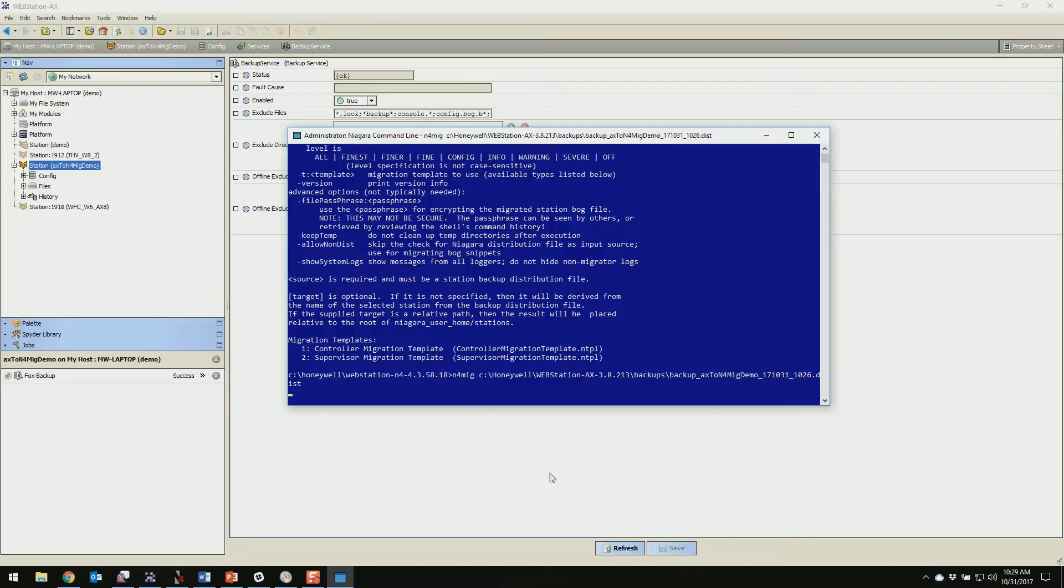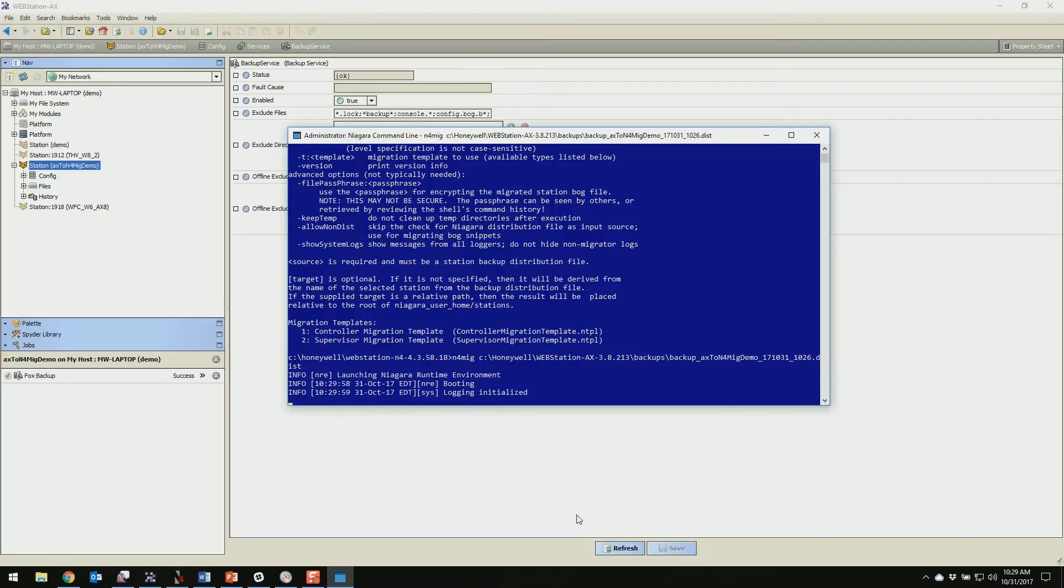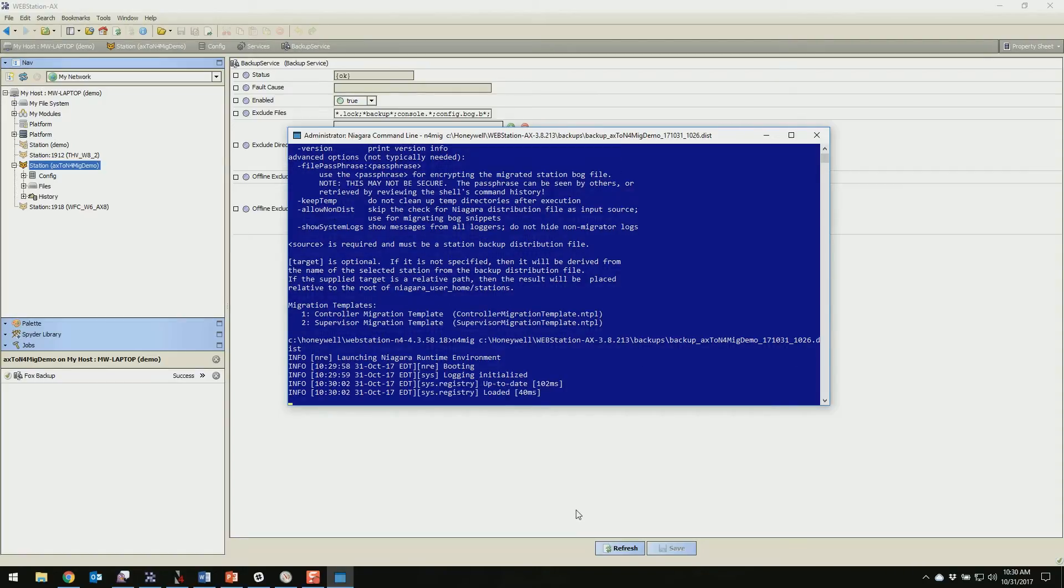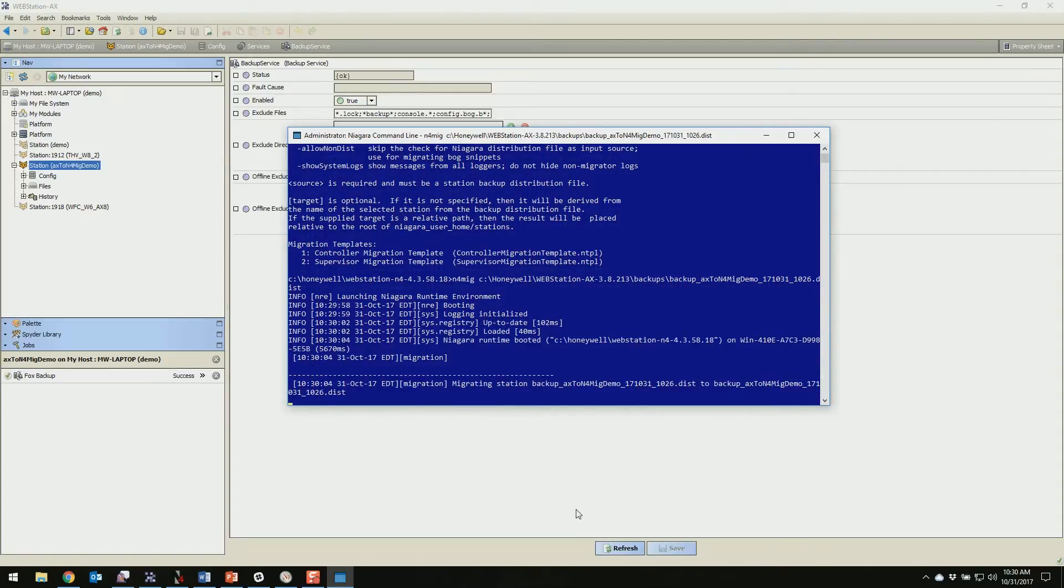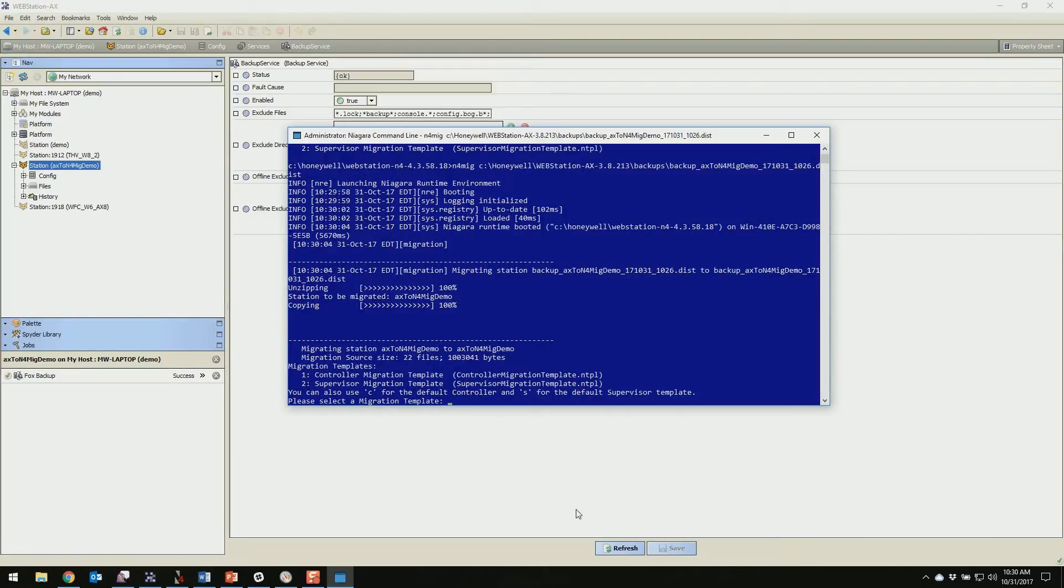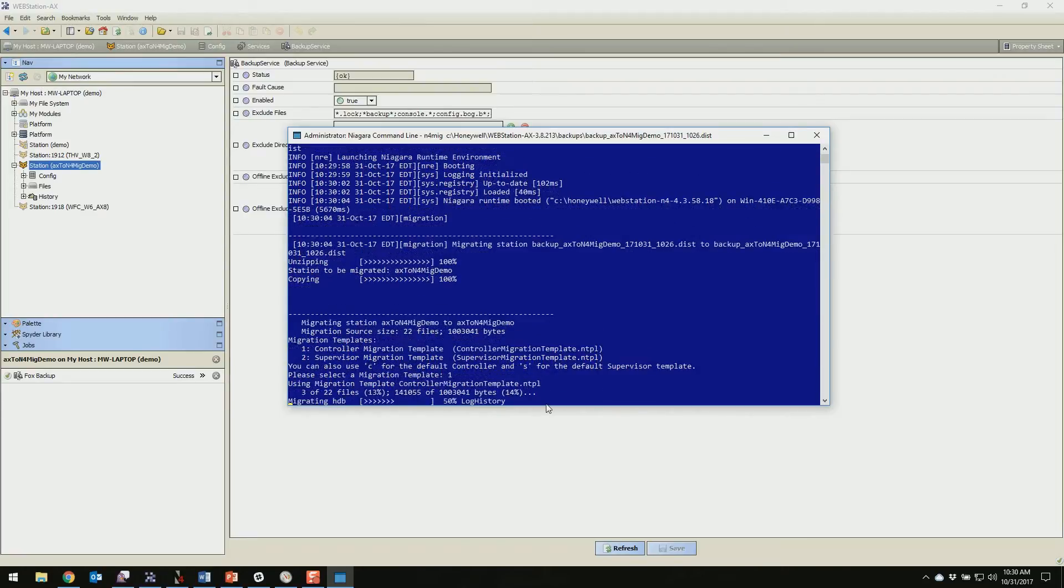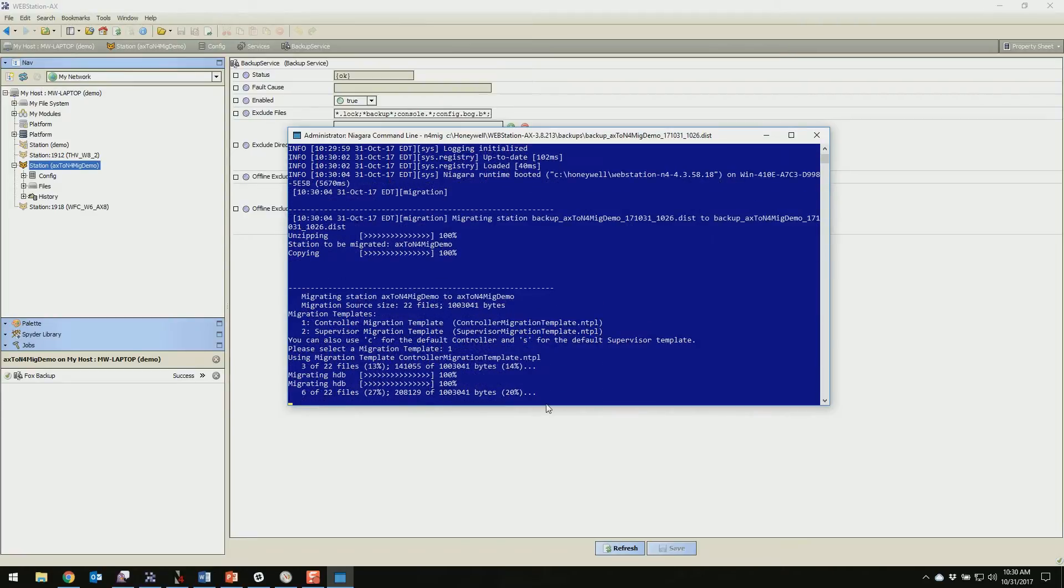It's going to run the migration on our distribution backup that we made in 3.8. Depending on the size of your station this could take a while, especially considering histories and things like that. But this is just a demo, it's only got a couple spiders in it so it's going to be quick. You'll get stopped at a portion here where it asks what template to use. This is going in a controller not a supervisor, so we're just going to hit 1. You can also hit C here as well.